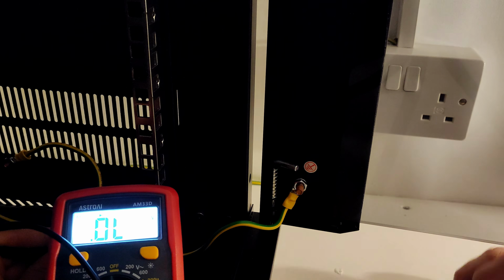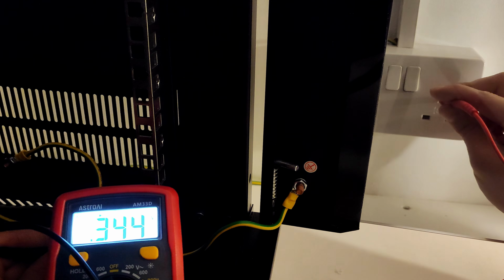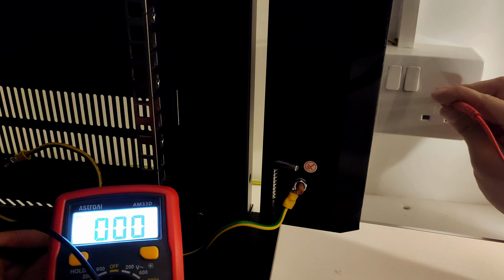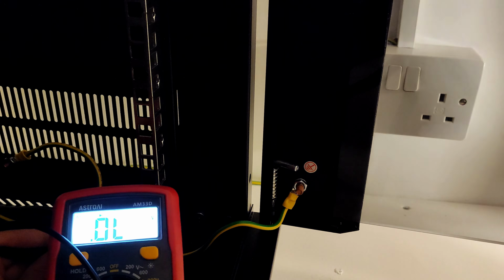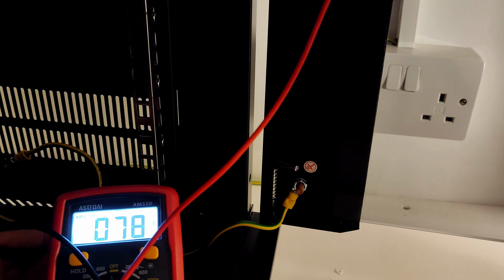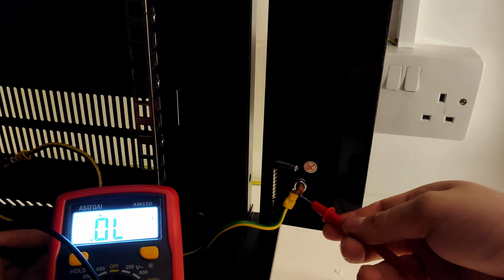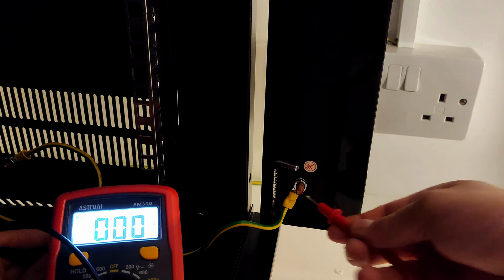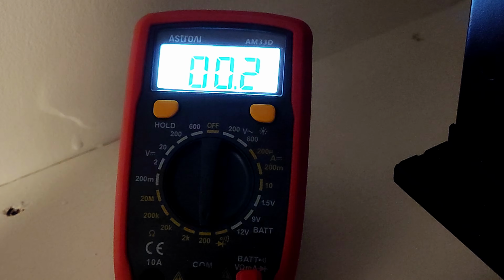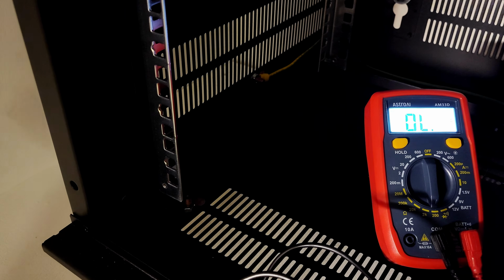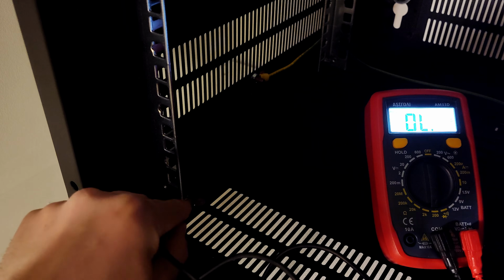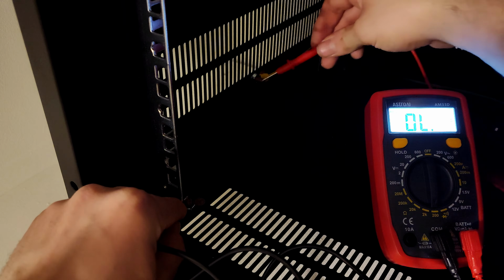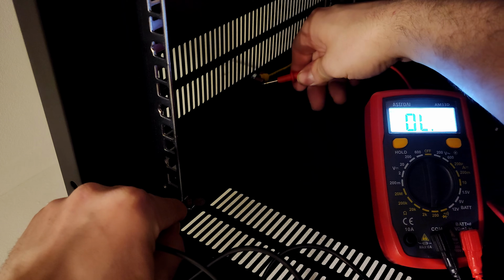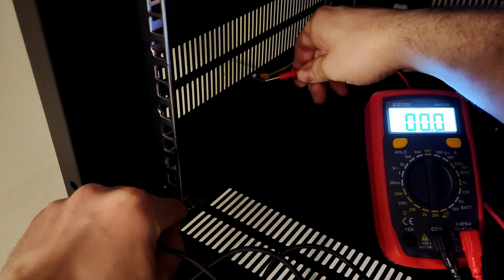So what are the benefits of using a star grounding setup? By converging all connections to a single point, you eliminate voltage differences that can cause interference or even damage to your equipment. After installing the grounding cable and tidying up all the connections, I recheck with the multimeter, and every grounding point shows a near 0 ohm reading, about 0 to 0.2, which confirms a solid and safe connection.